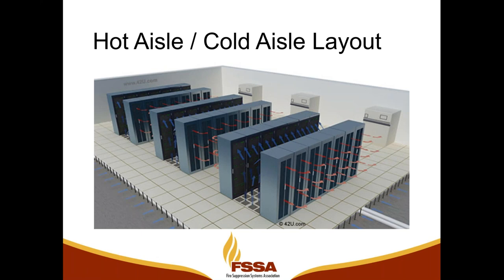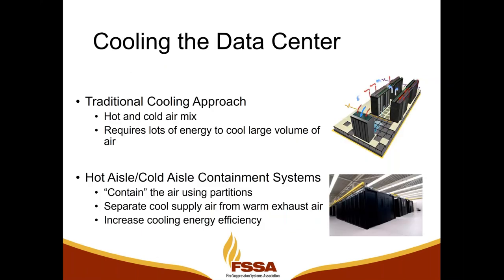So that hot aisle, cold aisle arrangement is important because then we can use that to our advantage for cooling the equipment. And so the traditional approach for cooling data center equipment was to deliver cold air at the cold faces of our aisles, and then allow that air to be exhausted to the hot side of the rack, and then that air goes back to the cooling unit, the CRAC unit, or a computer room air conditioning unit, or sometimes, if you know a brand name, you hear them called the Liebert units in the data center. And that strategy can only take us so far with regards to rack density. Once we exceed 6 kilowatts per rack, then that doesn't provide adequate cooling to the data center.